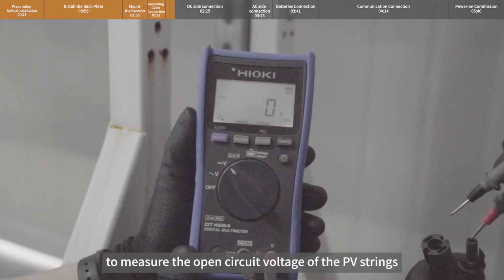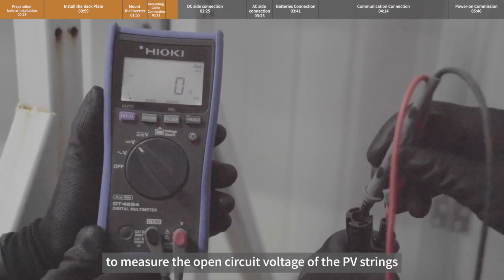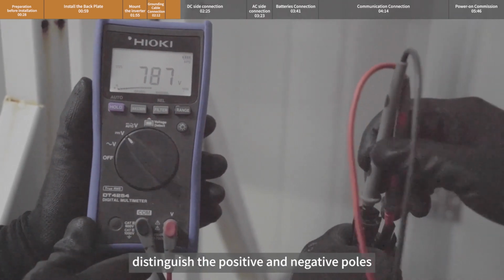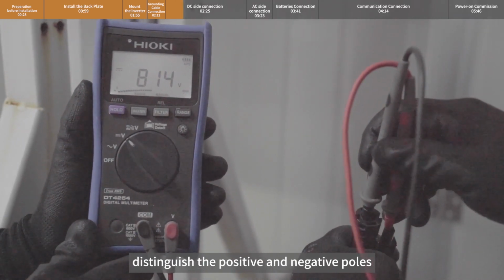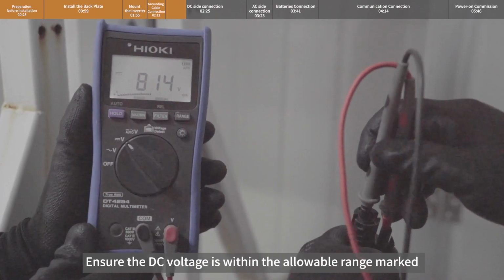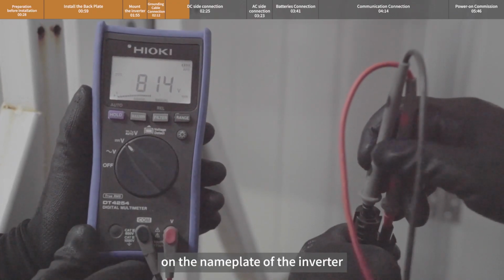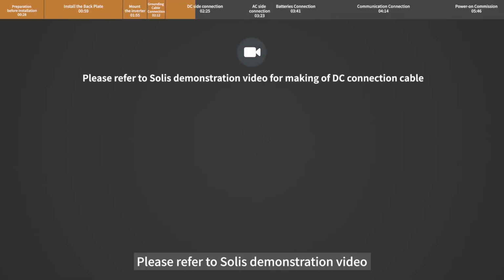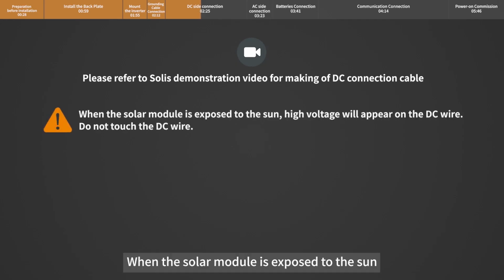Please use a multimeter to measure the open circuit voltage of the PV strings. Distinguish the positive and negative poles. Ensure the DC voltage is within the allowable range marked on the nameplate of the inverter. Please refer to the Solis demonstration video for making the DC connection cable. When the solar module is exposed to the sun, high voltage will appear on the DC wire.